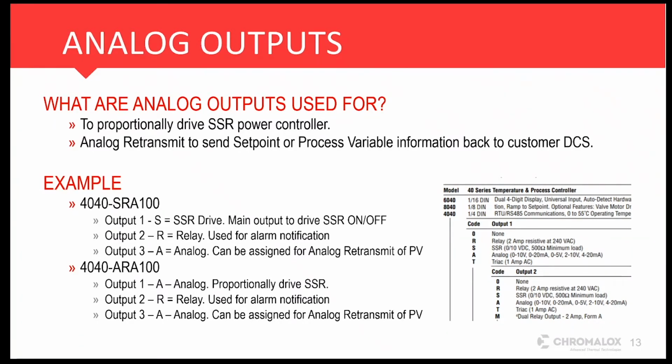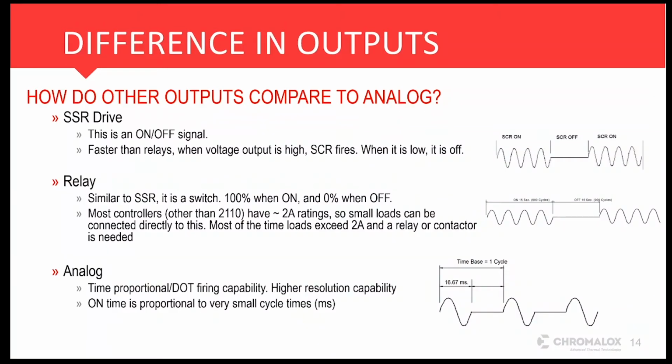But your controller specific, that's actually the first thing I generally ask when somebody calls in. What is the controller? And it's not, is it a 4040? It's a 4040 what? So now we understand how many inputs we have, how many outputs we have, and how we can now understand why it is not behaving as the customer anticipated.